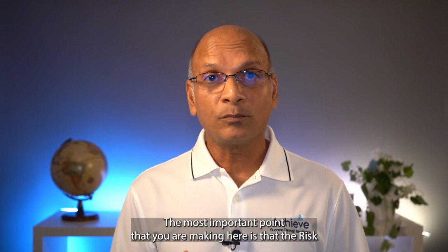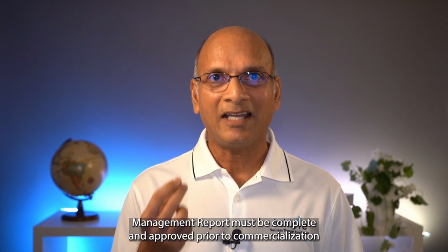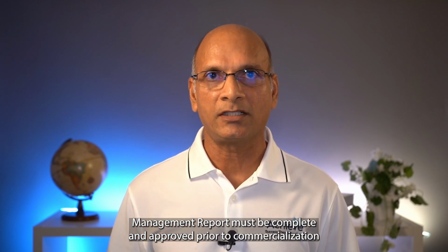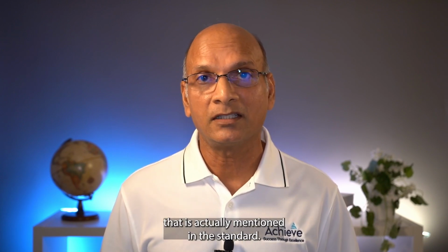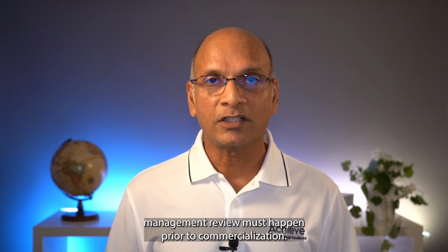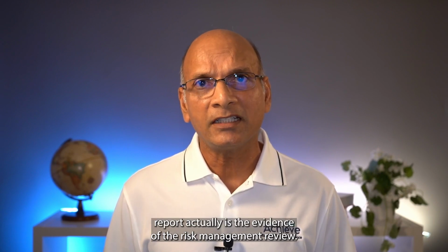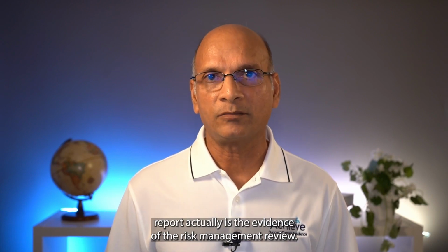The most important point that you are making, Ed, is that the risk management report must be complete and approved prior to commercialization. That is actually mentioned in the standard. It is a requirement of clause 9 that a risk management review must happen prior to commercialization, and the risk management report actually is the evidence of that risk management review.